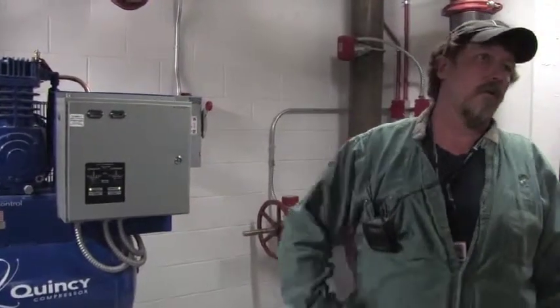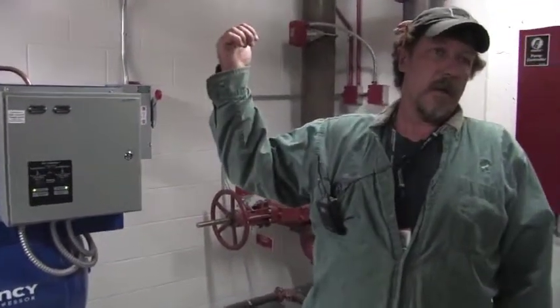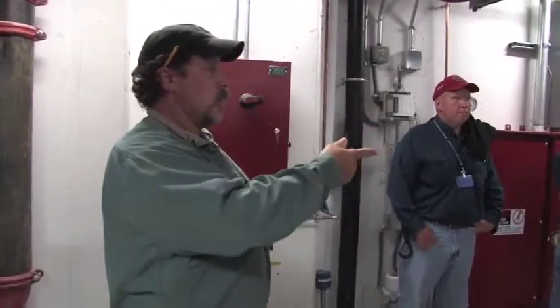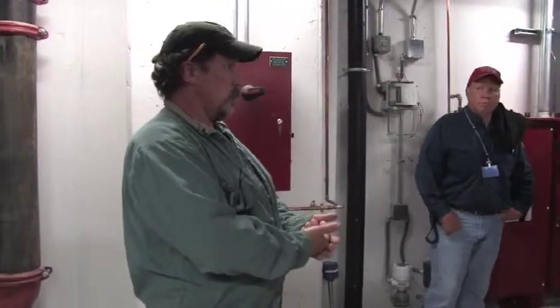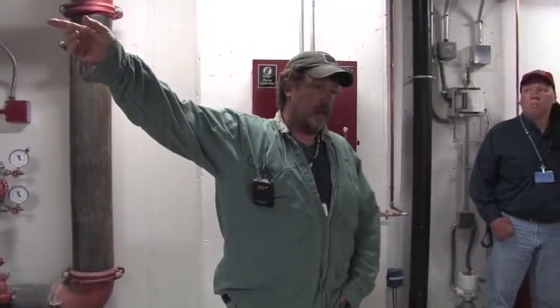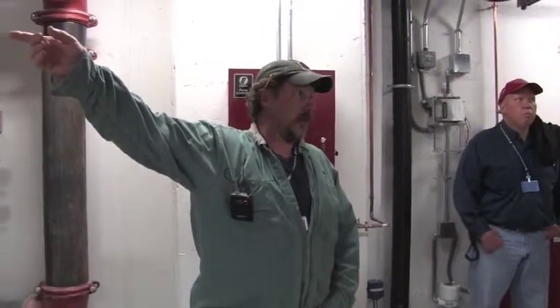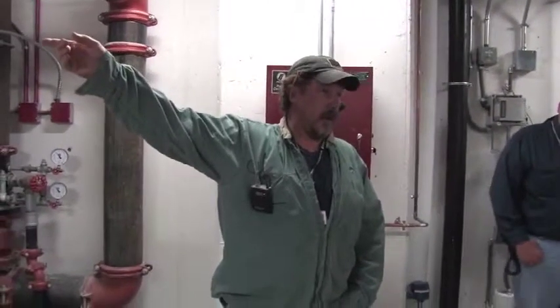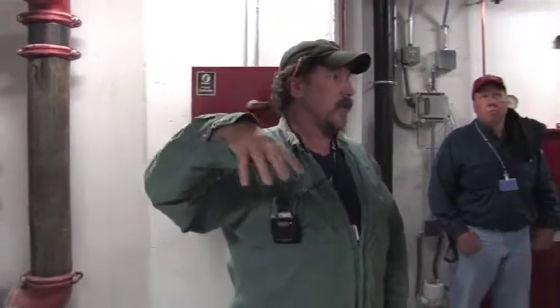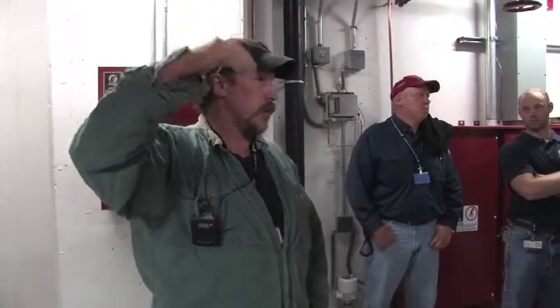Now we can take a walk over into the stairwell over here. And on the base of the risers, you have control valves. There's going to be two control valves on this side. One's for the high zone, one's for the low zone. And same with the stairwell over here. You're going to have one for the high zone and one for the low zone. There's one other sprinkler system down here that's its own zone off of the mains. It's for the tank room sprinklers, and that's directly in front of the elevator. And it's in the elevator lobby. You pop a tile, it's right above the ceiling there.